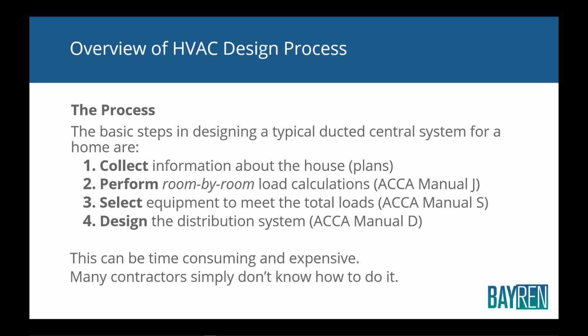As long as you show the dimensions of the walls and get the windows correct, that's the important thing. And then once you have that information, you also need to know what kind of walls, what kind of windows, are they dual pane, metal frame, vinyl frame, are they low E, how much insulation is in the walls, all that kind of stuff too. Once you have all that information, then your load calcs, and you want to do room by room load calcs, you do need software. I've done a few load calcs by hand very early in my career, and it was no fun at all. We would spend hours doing a load calc by hand with a calculator. And then my boss would come by and say, oh, that looks great. Now do it with better windows. I'm like, oh my God, are you kidding me? And so you had to go through and basically redo the whole thing, because it was all written down on a worksheet. So we had a lot of erasing, a lot of stuff like that.